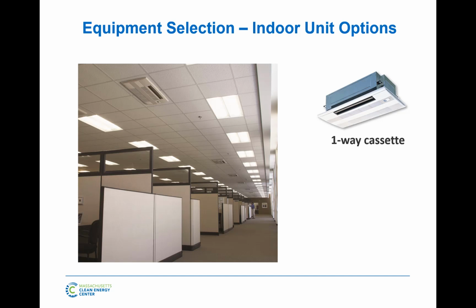Where they're becoming more common is this is actually becoming very common in residential applications. So the beauty of these is that they can be completely serviced from the bottom. So service access can be completely done from the bottom on these. So they're being used in residential applications where there's maybe not an attic to put the equipment where it can be serviced later, but you have to go service it, you pull this faceplate down, and you get access to everything there.